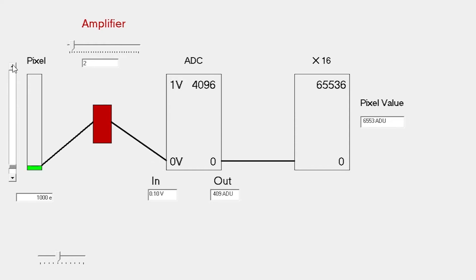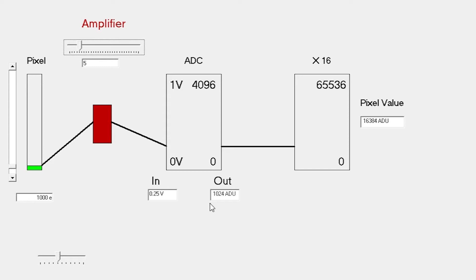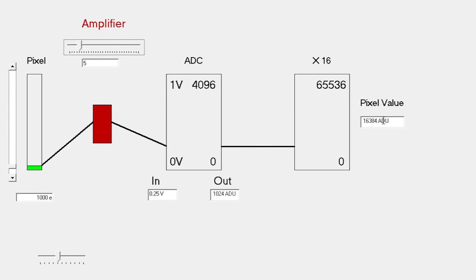One other thing to mention related to gain: we have this slightly special case where there is a gain of 5. At a gain of 5, we have this interesting situation where the number of electrons is roughly equal to the 12-bit ADC output. Here we have 1,000 electrons, we have slightly over 1,000 on the ADC output. So the conversion here is basically 1 or unity, and this gets called the unity gain factor. There's nothing particularly special in terms of any features or performance of the camera around this gain of 5, or what we call this unity gain situation. It's just a situation where we have 1,000 electrons equaling 1,000 ADU units at the output of the ADC, even though we end up reporting that as 16,000 ADU counts at the computer.